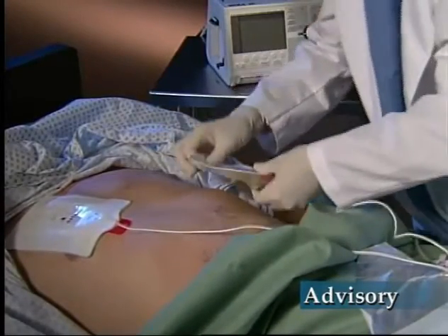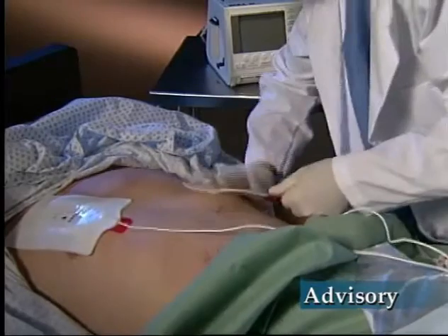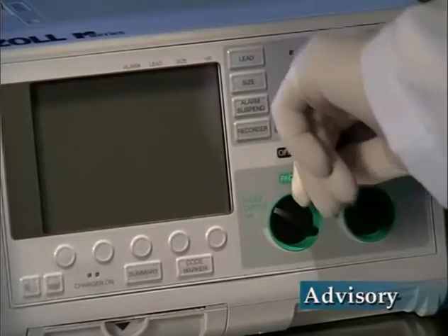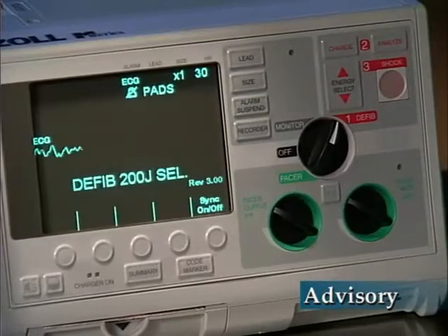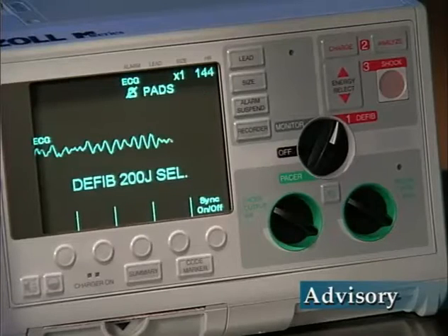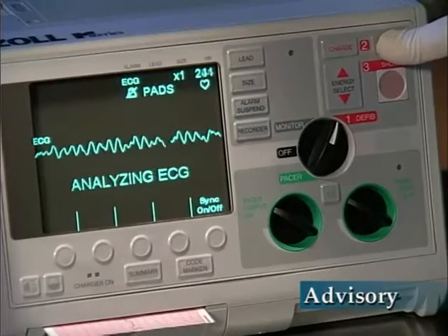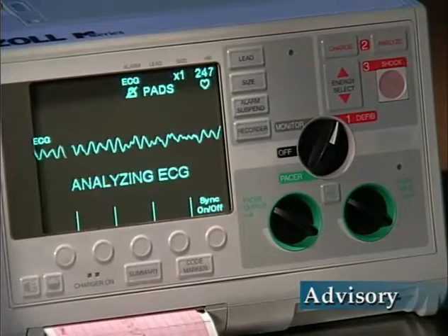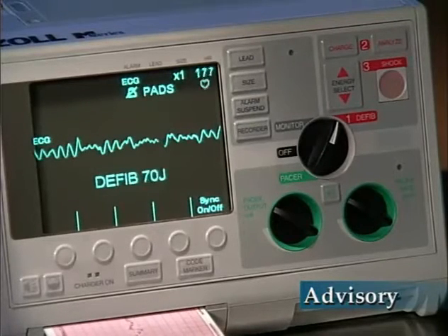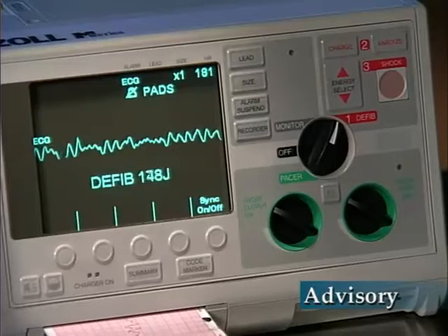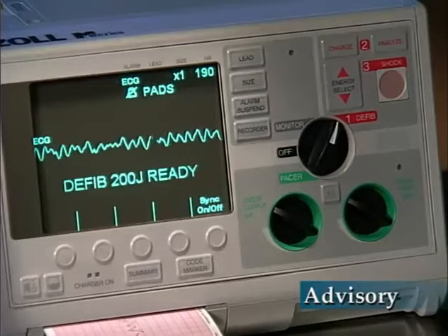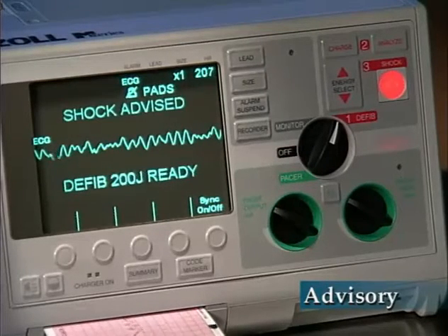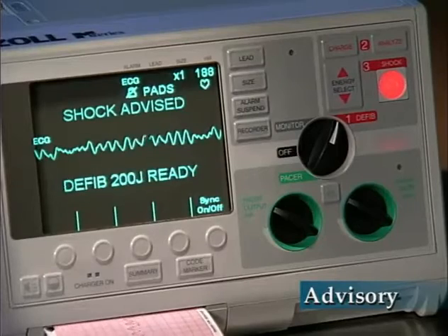To use the advisory feature, the selector button must be turned to Defib. The unit will display Defib 200 joules selected on the monitor. Press the Analyze button to begin analysis of the patient's ECG rhythm and to detect any shockable rhythm. Analyzing ECG will be displayed while the patient's ECG is analyzed. Once the analysis is completed, the unit indicates whether or not a shock is advised.